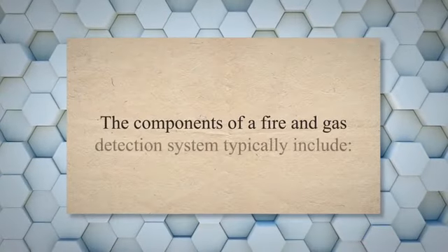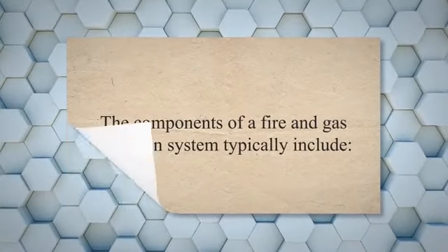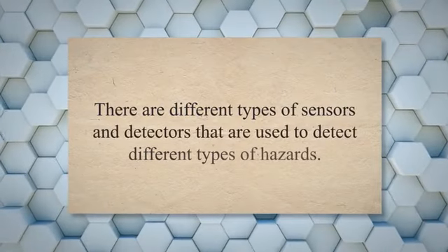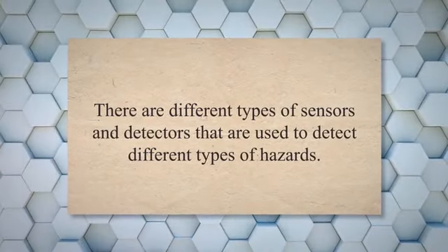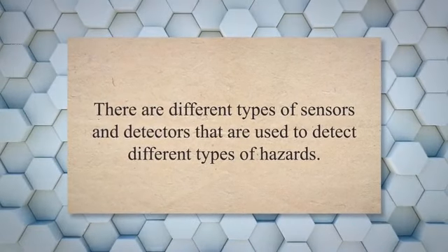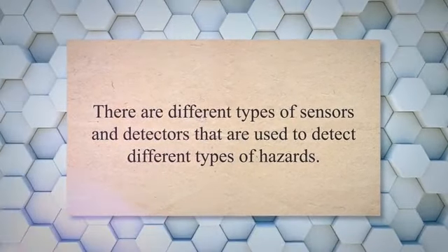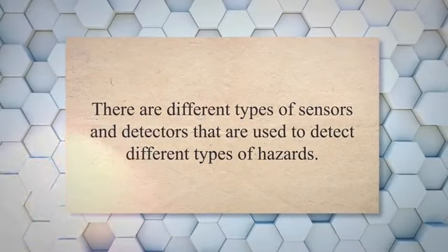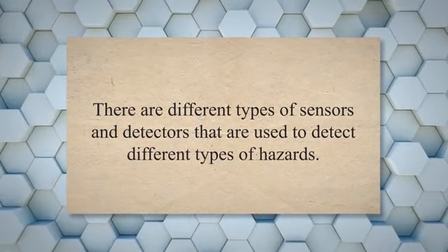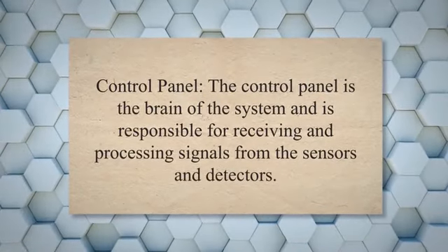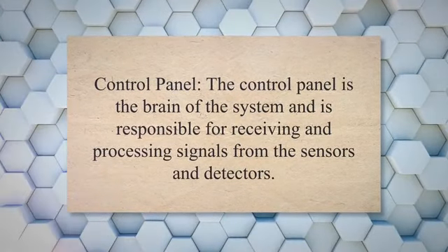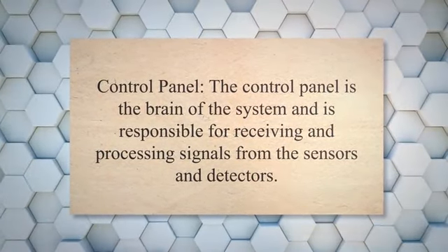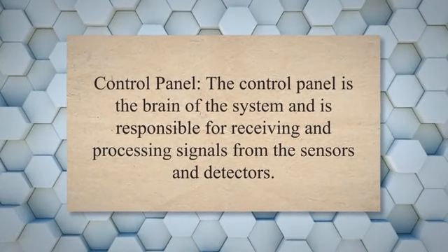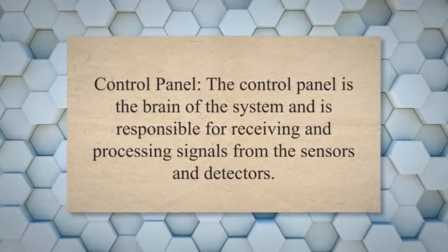The components of a fire and gas detection system typically include sensors and detectors. These are the primary components of the system and are responsible for detecting the presence of flammable or toxic gases, as well as smoke or flames. There are different types of sensors and detectors that are used to detect different types of hazards. Control panel. The control panel is the brain of the system and is responsible for receiving and processing signals from the sensors and detectors. It also activates the appropriate alarms, warning signals, and safety measures when a hazard is detected.